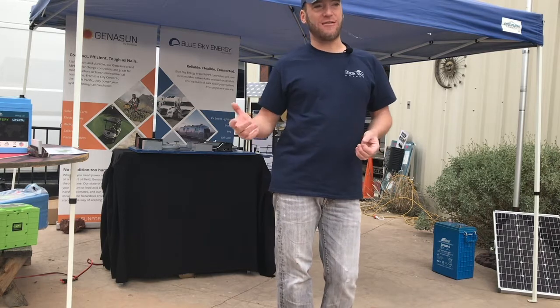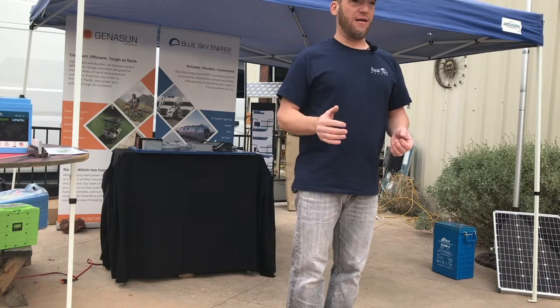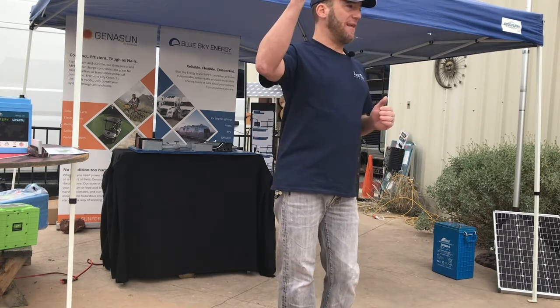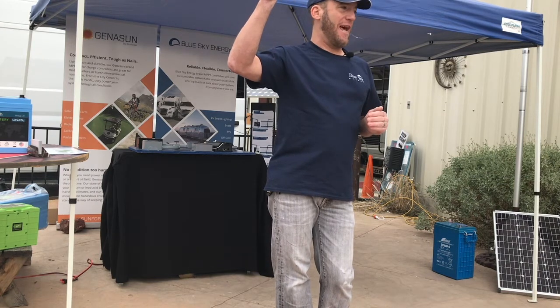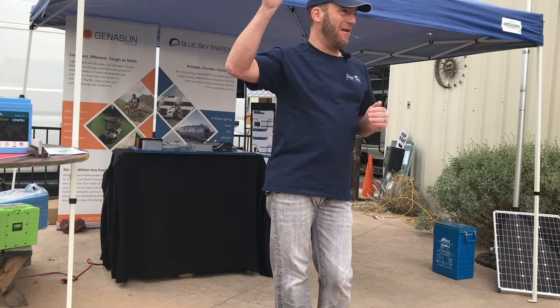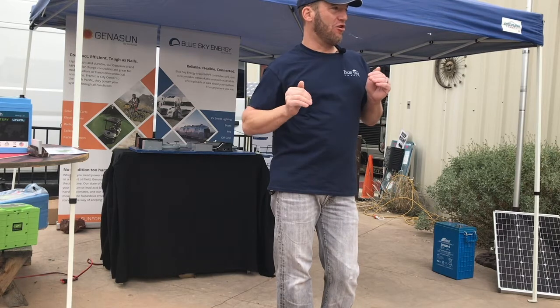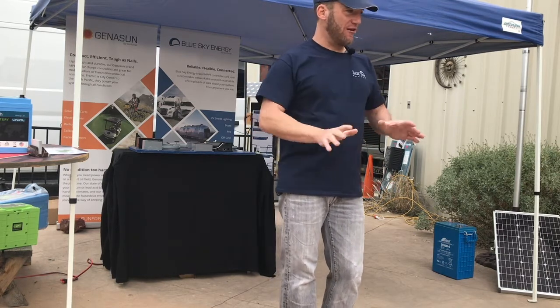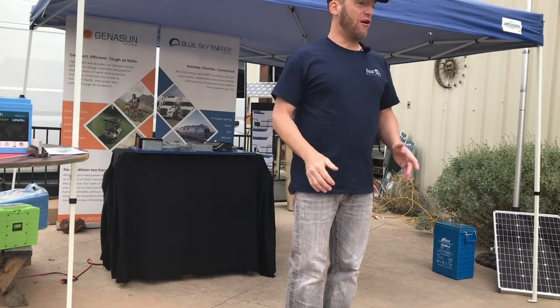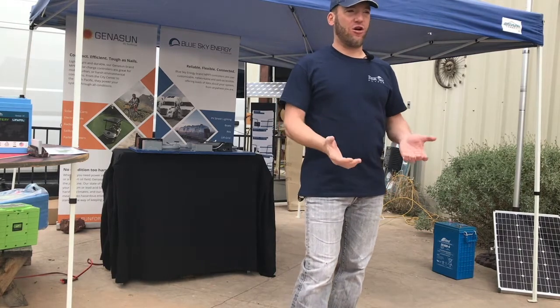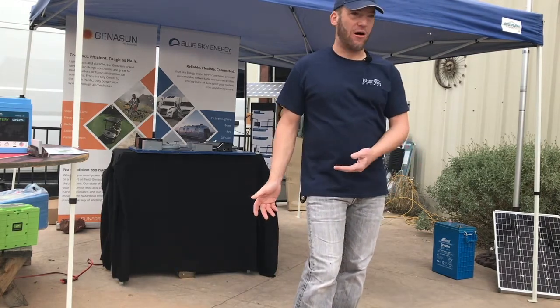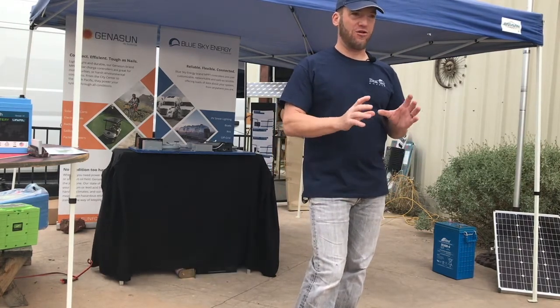Now, if you had the shunt installed, that's a moot point, because every day your controller is going to get to the absorption voltage, although it'll only hang out there for a couple seconds. But the fact that it got there even for 2 minutes a day keeps sulfation away. So you don't really need to program a storage charge profile if you have a current shunt installed — I'm only talking about standalone charge controllers.